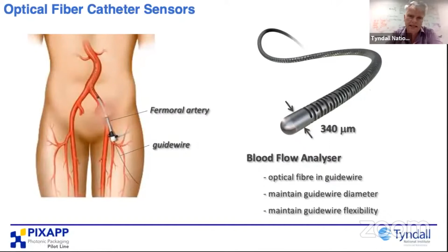And in this particular project, we integrated a fiber sensor. It was actually for measuring blood flow using Doppler velocimetry. So basically, feeding back into an optical system, you interrogate the beam, and based on the Doppler shift from the blood cells, you can monitor the flow. So it's like a simple sensor. The important point here is, again, it's a platform. So it's integrating optical fibers onto an extremely small and flexible guide wire. So it could also be a catheter, and using that as a sensing platform.